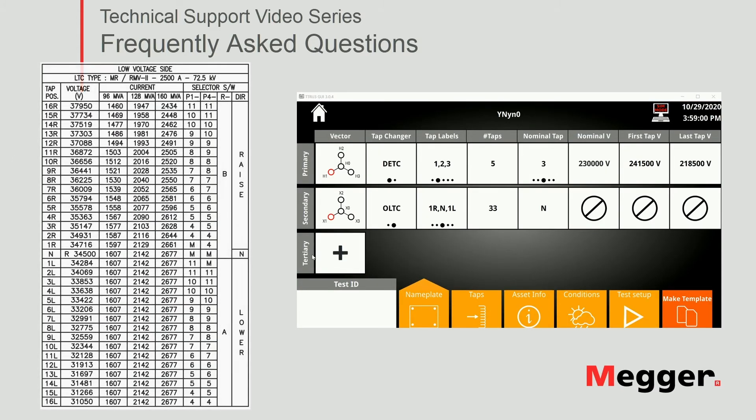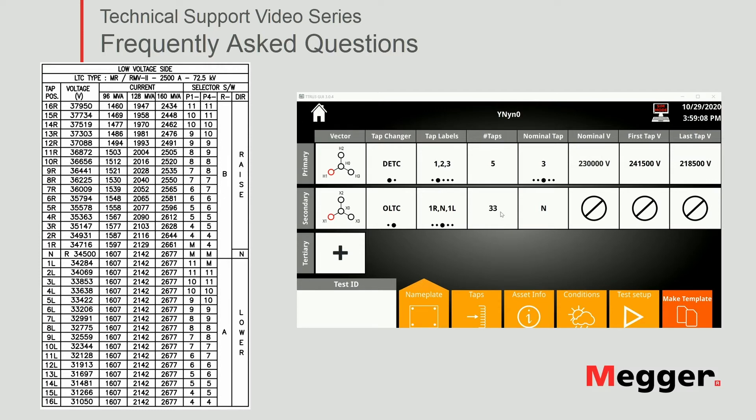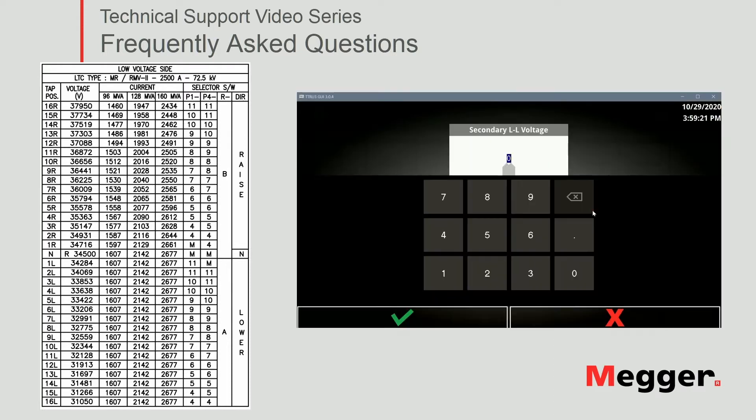Now for our low side we see here from the nameplate we have 33 taps as it's already indicated and the labels do match what we have already selected. So yes, our nominal tap is N. Nominal voltage is 34,500.